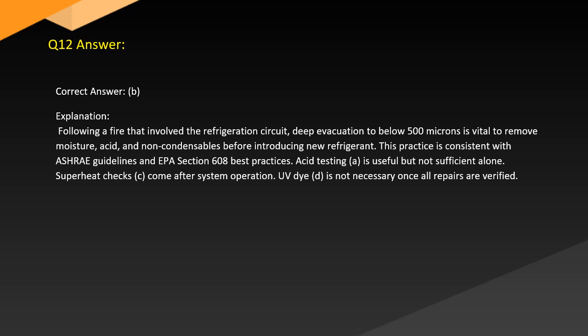Answer. Correct answer: B. Explanation: Following a fire that involved the refrigeration circuit, deep evacuation to below 500 microns is vital to remove moisture, acid, and non-condensables before introducing new refrigerant. This practice is consistent with ASHRAE guidelines and EPA Section 608 best practices. Acid testing is useful, but not sufficient alone. Superheat checks, C, come after system operation. UV dye is not necessary once all repairs are verified.